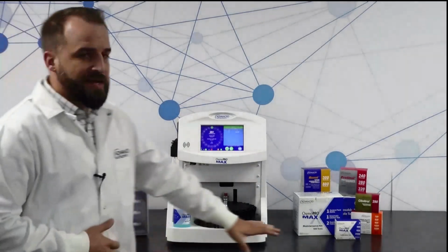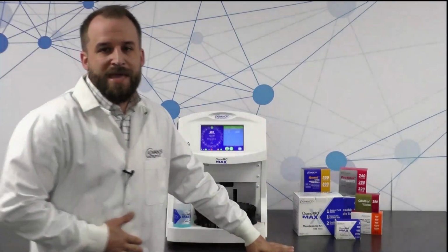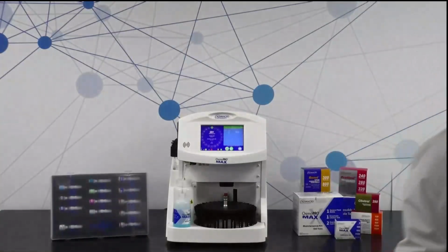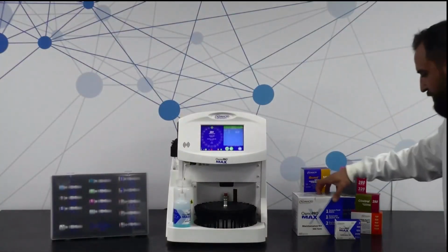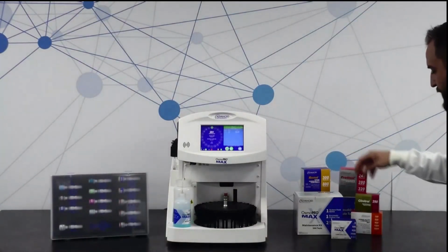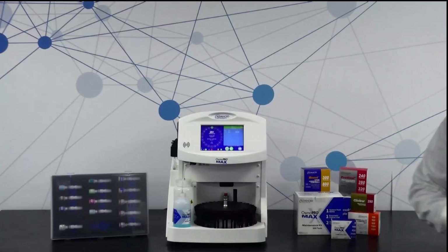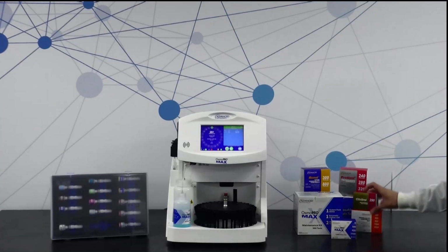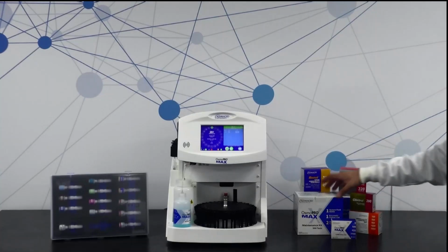Everything over here on the right is what you'll typically see from a consumable perspective for this instrument. So what's great about the OsmoPRO MAX is when you get the instrument delivered, you order a convenience kit to make sure that you have everything you need to get the instrument up and running and run a few tests in the meantime. You're going to get everything you see here.